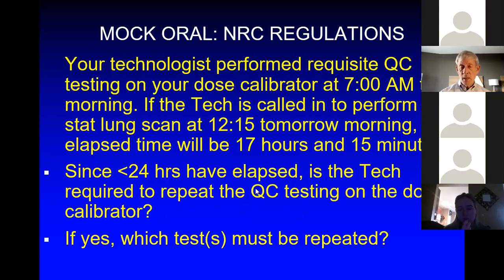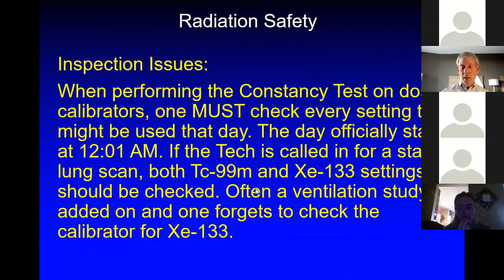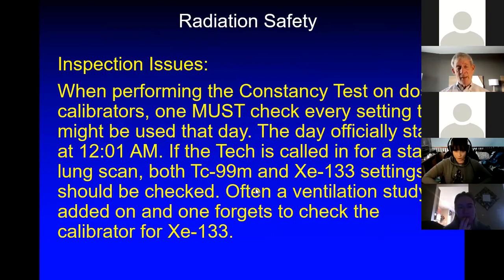The real question here is, is it every 24 hours or is it every calendar day? Every calendar day. Good, it is every calendar day. And so here's what happens. If you draw a dose at 11:55 p.m., you're good. If it's 12:01 a.m. or later, you've got to repeat the constancy test, at least on the isotopes that you're going to use. So you come in for a stat lung scan, you're probably going to check both technetium and xenon if you're a xenon user, but it's every calendar day. And that day starts at 12:01 a.m. And so that's something to remember.